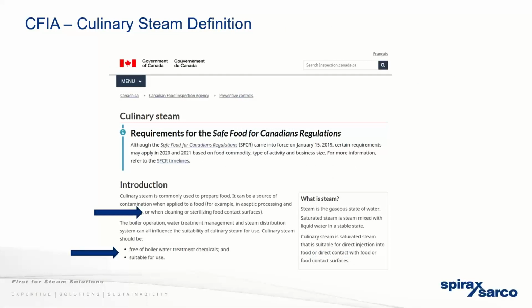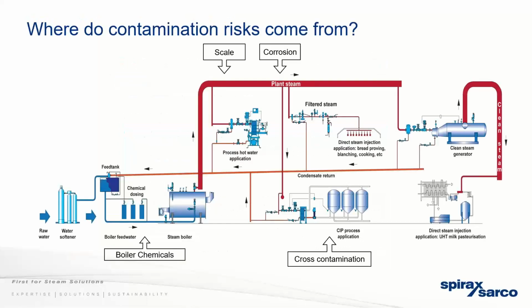In the CFIA guidelines, the requirements for Safe Food for Canadians, they describe culinary steam as steam that will be used when cleaning or sterilizing food contact surfaces. And they also say it should be free of boiler water treatment chemicals. So these two points make it pretty clear that you can't use a boiler with chemicals in it on food contact surfaces. For this reason, we would use clean steam generation to take out those chemicals if we were using direct injected steam in hose stations.